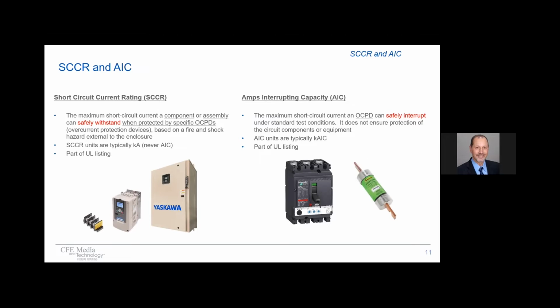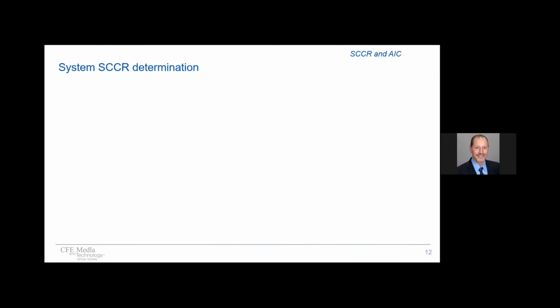That's a key differentiator here between what we call SCCR systems and devices versus devices that actually have an interrupting capacity on the right. And of course, on the right-hand side, those devices always have an AIC rating, an interrupting rating. Now, just remember, SCCR is what something can withstand, and AIC is only for devices meant to interrupt. But often, SCCR and AIC rated devices are combined. In such cases, we wind up with a withstand or SCCR capability based on the combination of these devices.